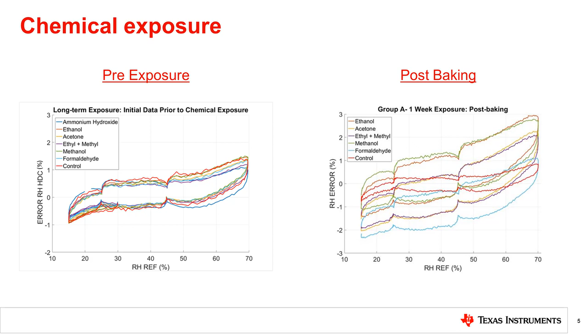High-dose exposure testing has been done in this area, and the graph on the left shows the humidity sensor output prior to chemical exposure, while the one on the right represents the impact of various VOCs. Baking the units that were exposed for the most part brings the units back to almost normal, with acetone, ethanol, ethyl plus methyl, and methanol being the chemicals that cannot be completely baked out of the polymer and still affects the measurement results, as shown in the graph on the right, compared to the unexposed units in the graph on the left.